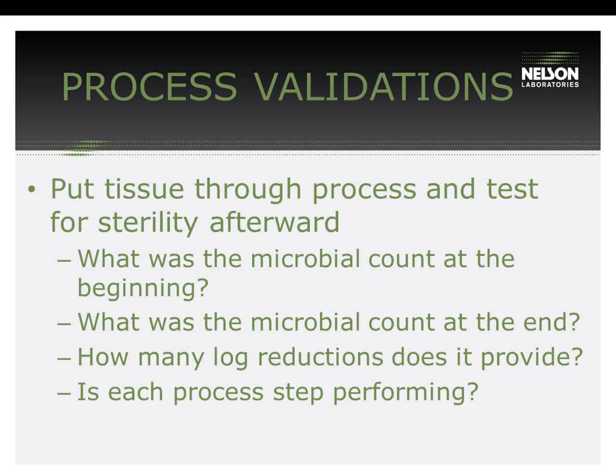And one of the first ones is the example where oftentimes you may just take tissue, maybe just typical tissue, or maybe something you might feel is kind of worst case tissue, and you put it through the proposed process and test for sterility afterwards. Now that is very simple. It seems intuitive, and it is undoubtedly very easy, but in most cases you can gather almost no real understanding of the capability of your process when taking this approach.